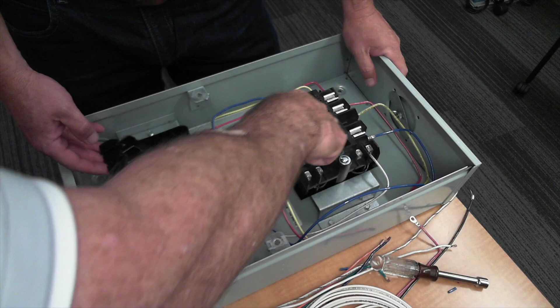One thing to think of is when you have the voltages open, these right here are still hot. It's just the top side of it when you open them that kills it and turns it off. That's a good point, because there are times, like when testing in substations, where they want you totally disconnected because they don't want even the possibility of a backfeed.